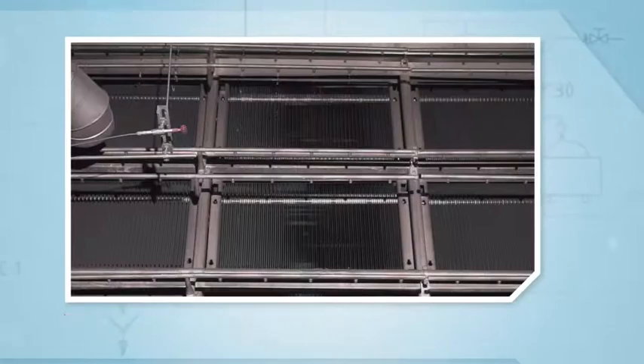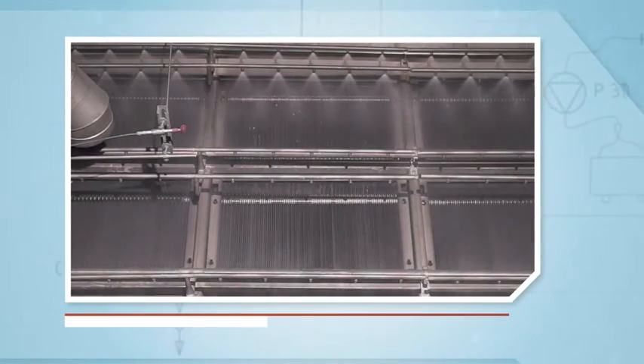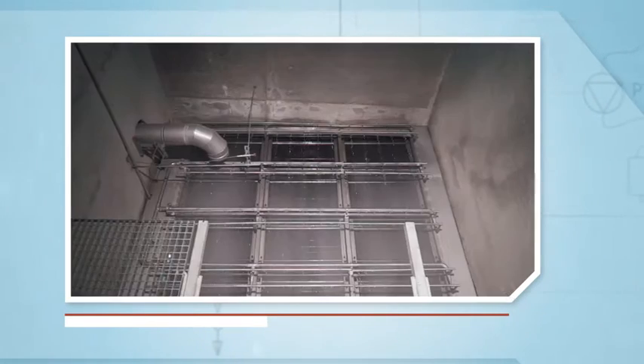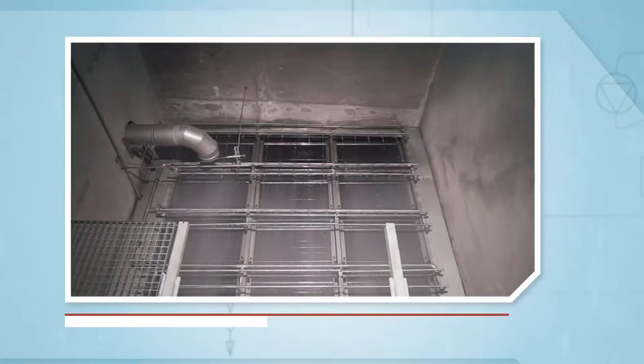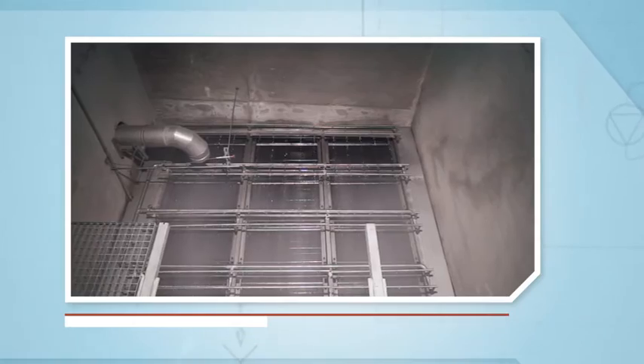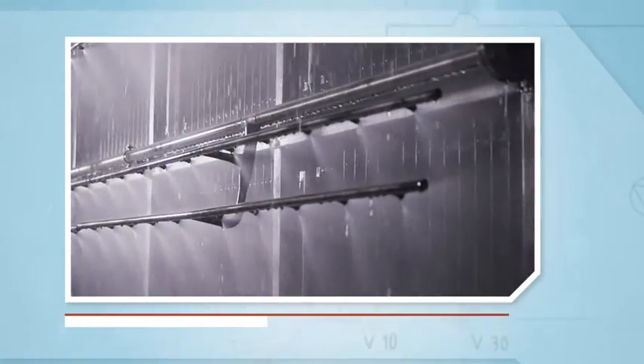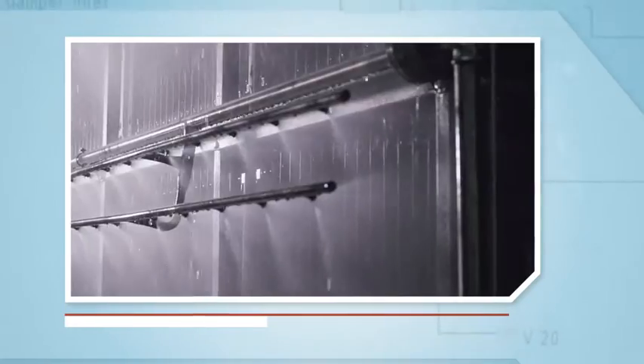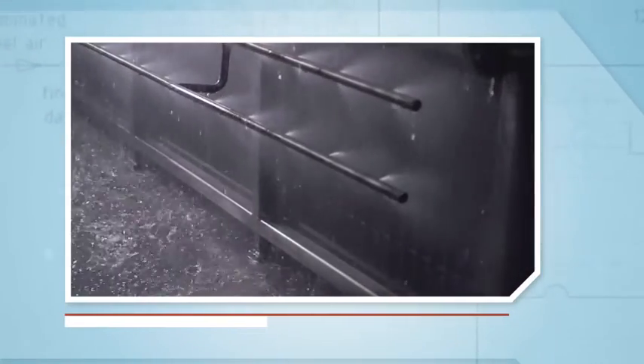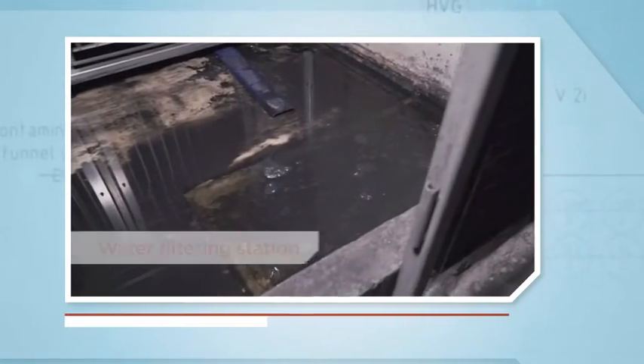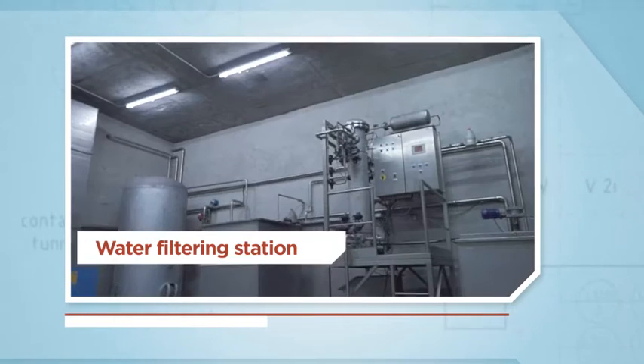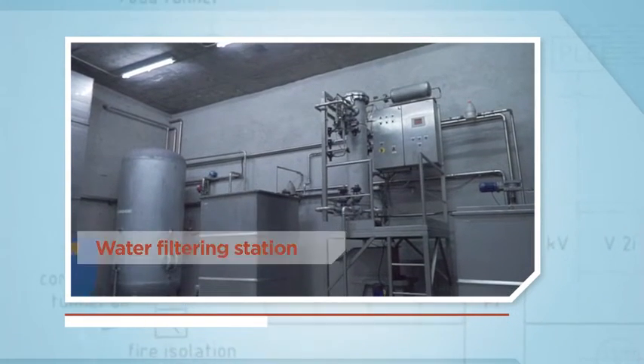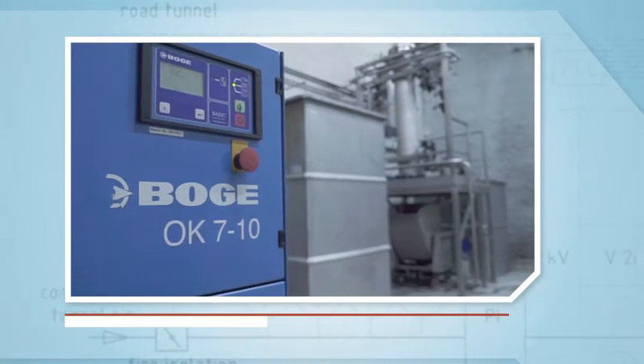The particle dirt collected on the electrostatic precipitator's collector plates is regularly removed by washing the filter with additive-free water, which is sprayed by lines of nozzles installed in front of and behind the filter. The rinse water of the collected pollutants is pumped to a water filtering station that cleans the water, allowing the reuse of most of the water for the next washing cycle.